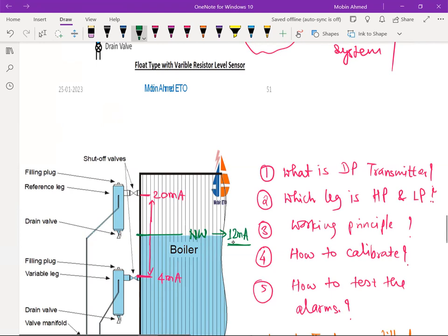Now we can have a different level. We can have the alarm or we can have the start and stop of the pump. Let's see how we are going to adjust that. Suppose it reads 12 milliampere at the center. We can very precisely do 14 milliampere, 16 milliampere, and 18 milliampere, then finally 20 milliampere. In the same way 10, 8, then 6 and 4 like this.